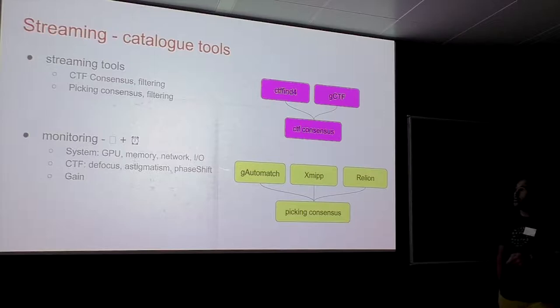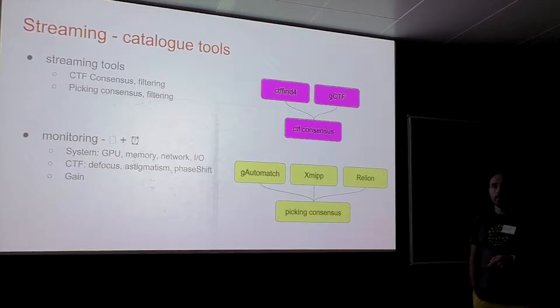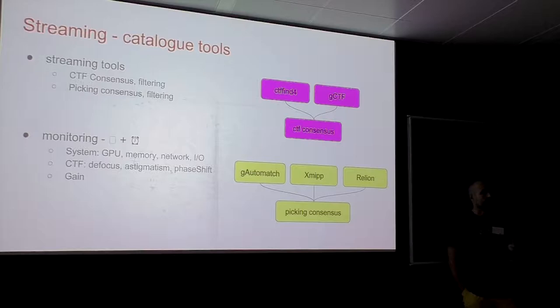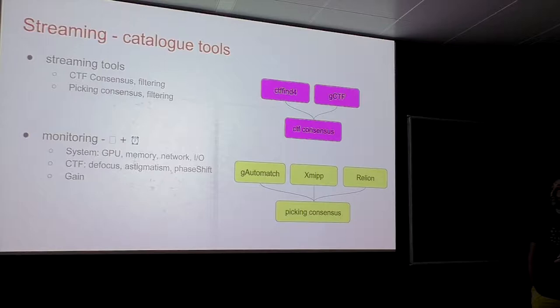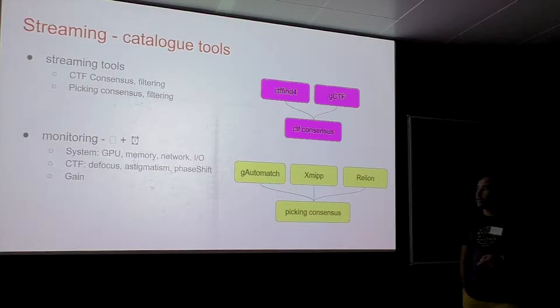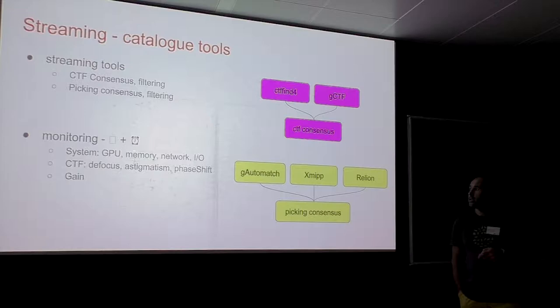Monitoring is also built into Scipion. Monitors are processes that check how things are going during your acquisition or workflow. There are three main monitors. One is the system monitor: it monitors GPU, CPU temperature, memory, network activity, and hard drive activity. You can also monitor CTF — focus, astigmatism, and phase shift. The monitors have built-in alerting: you configure the email settings, and the monitor sends you an email when values go above or below thresholds you specify.